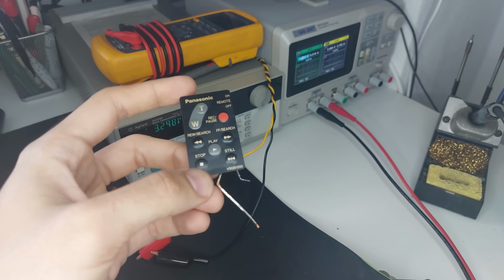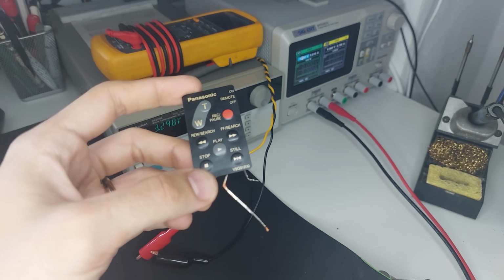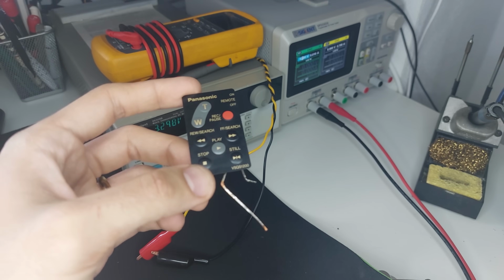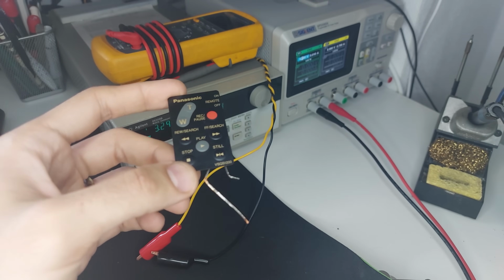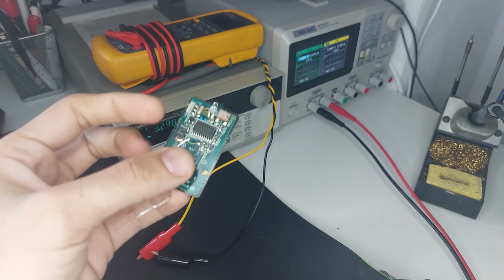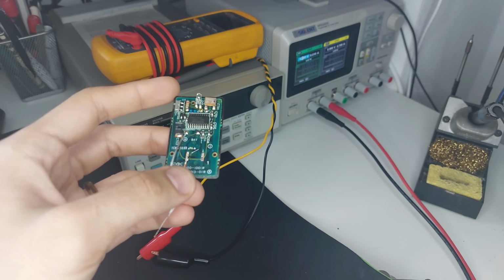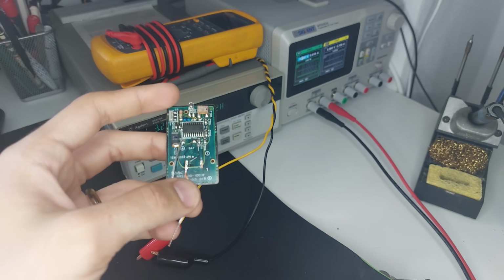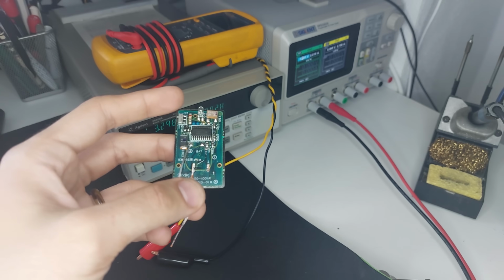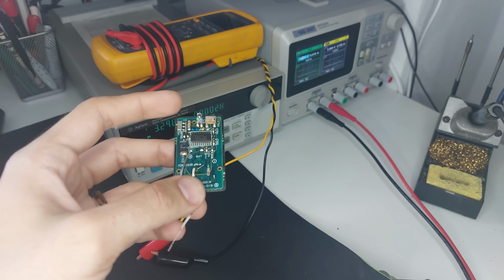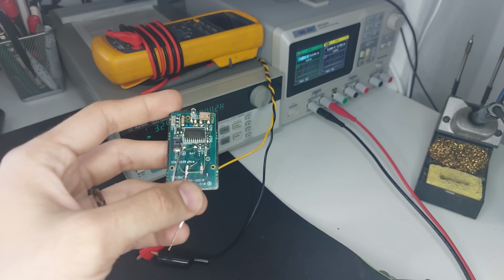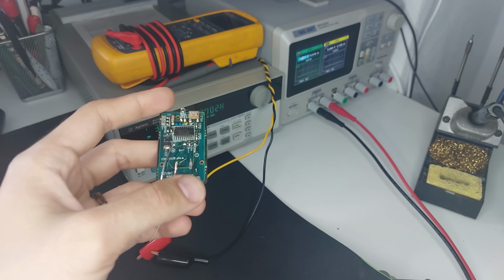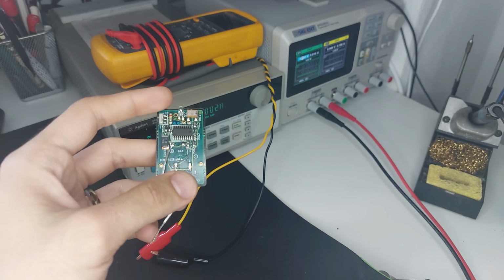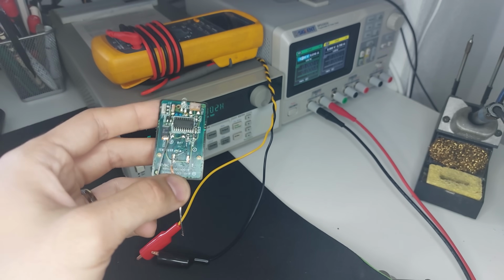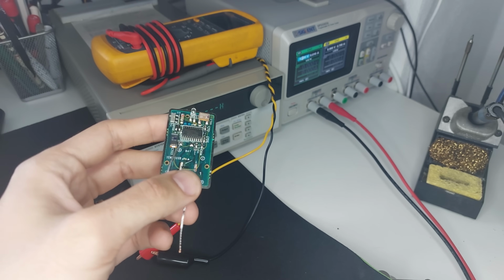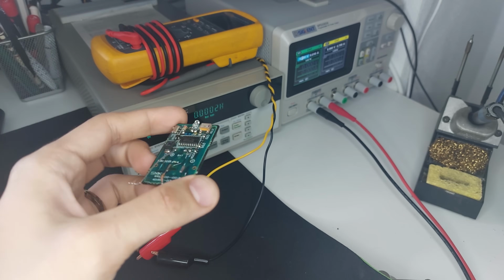So when I was measuring the current consumption of one of those things, I used to use the microcurrent, right? Which has a reasonably low burden voltage shunt resistance. So compared to what was previously used to measure the current through that device, which was a plain 1 ohm resistor in series with the supply, which they connected to the oscilloscope to use as an improvised shunt, the 10 milliohm shunt resistor from the microcurrent was much, much smaller. So they could see that instead of drawing a peak of a couple of hundred milliamps from the battery, the device would actually be able to draw up to an amp in short bursts. So basically, that was a discovery that meant some things had to be reconsidered.